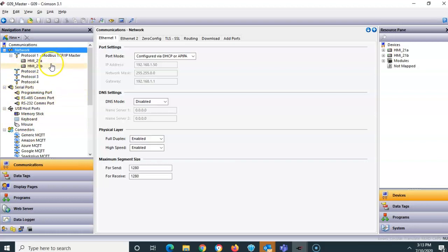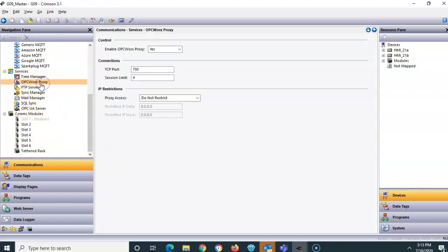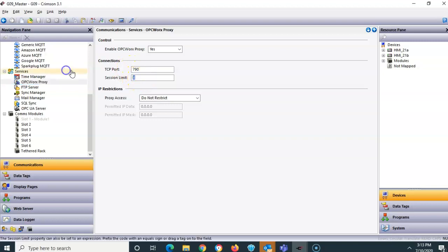In the communications section under services, I went into a section called OPCWorx Proxy and set it to be shared. I set up four sessions — apparently this OPC proxy supports up to four HMIs polling at the same time. If you try to enter a larger number, Crimson pings you with four as the maximum. I went ahead and saved that in the database.